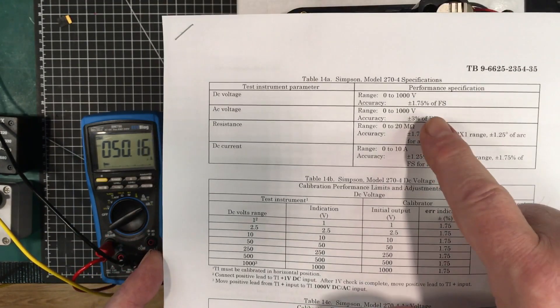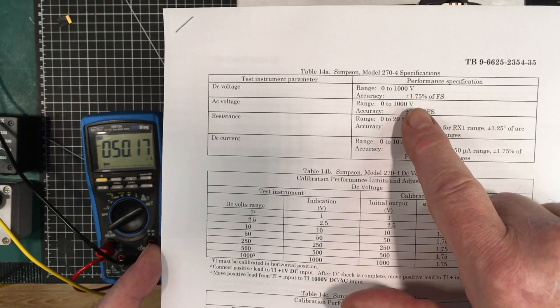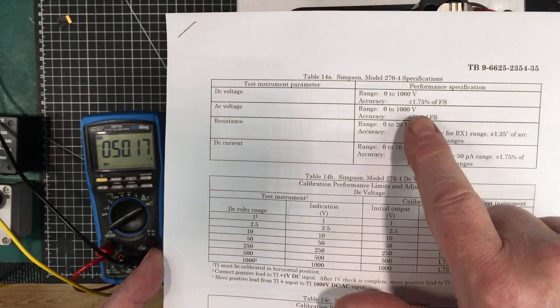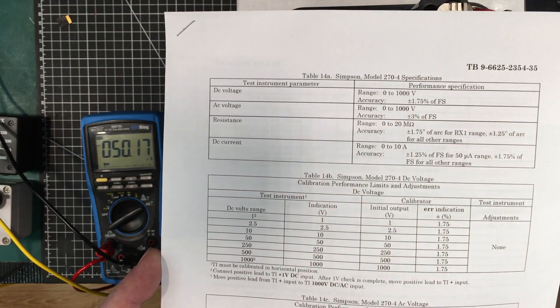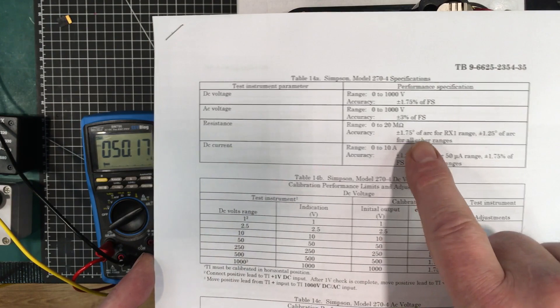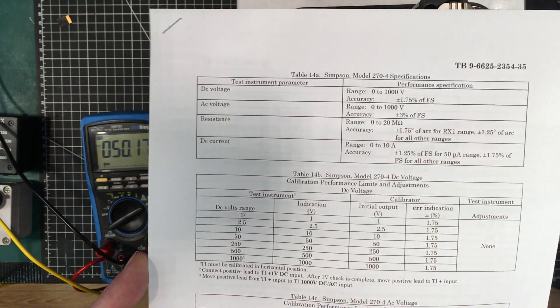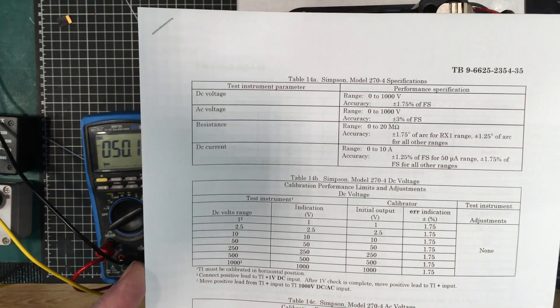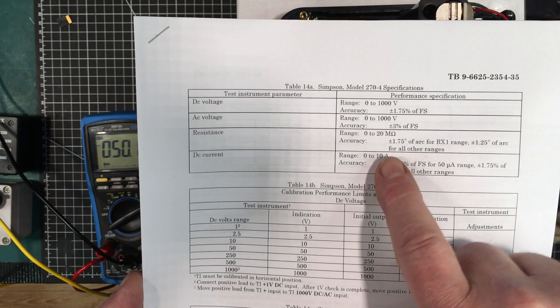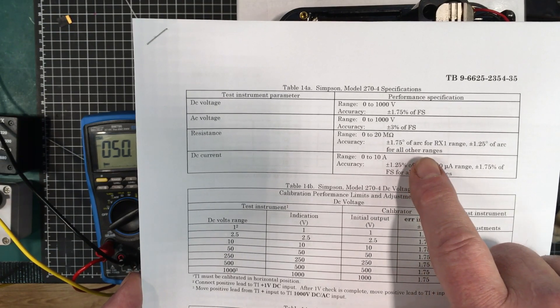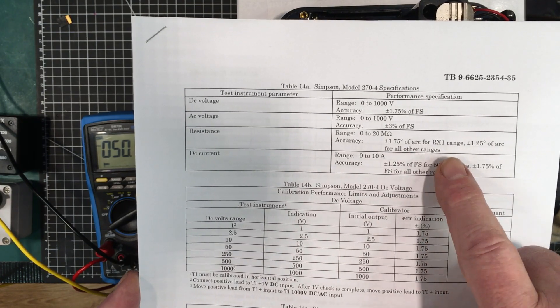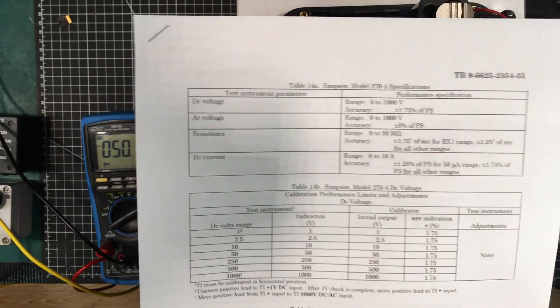Here's our tolerances and performance specifications. For DC voltage plus or minus 1.75% of full scale, AC voltage plus or minus 3% of full scale, resistance plus or minus 1.75 degrees of arc.